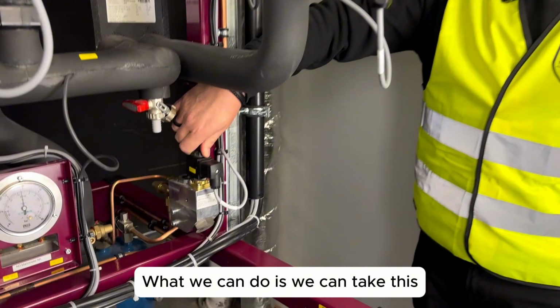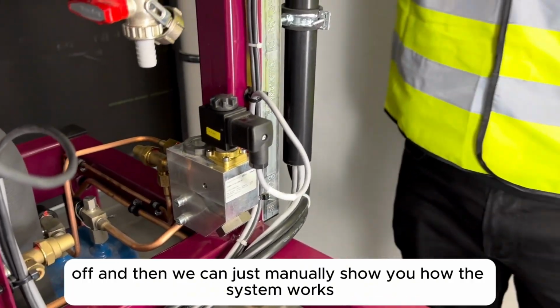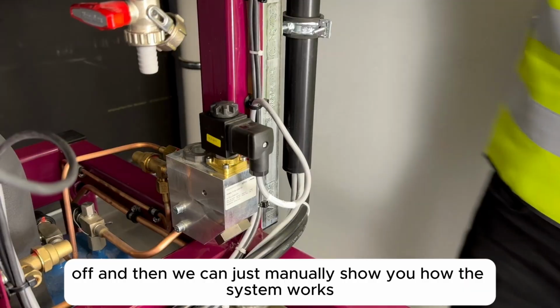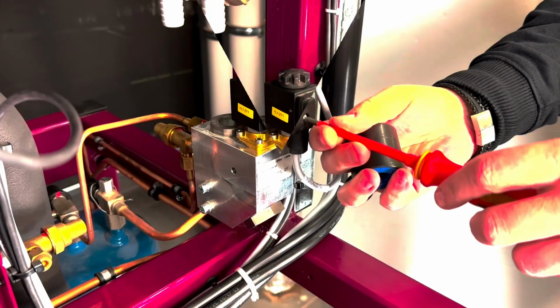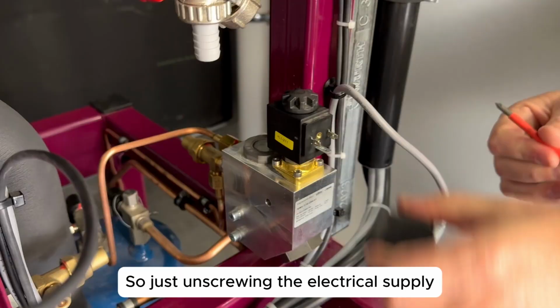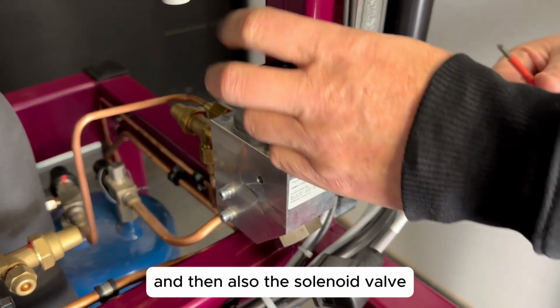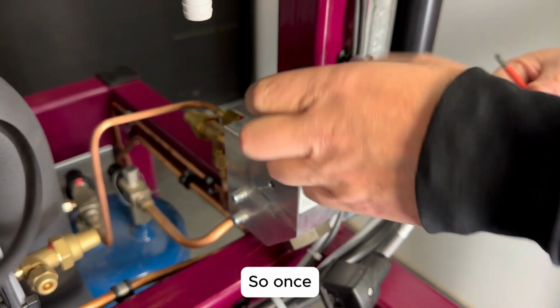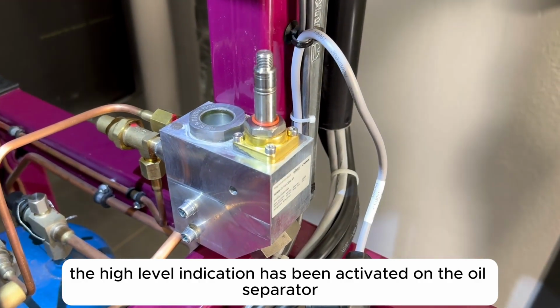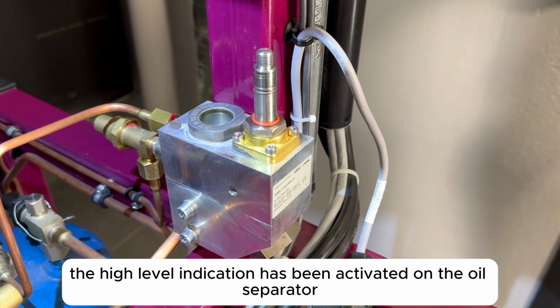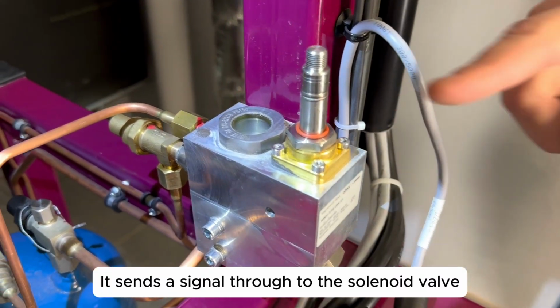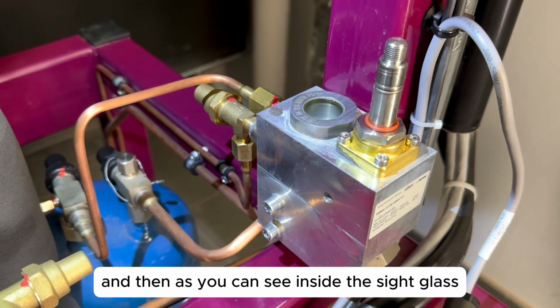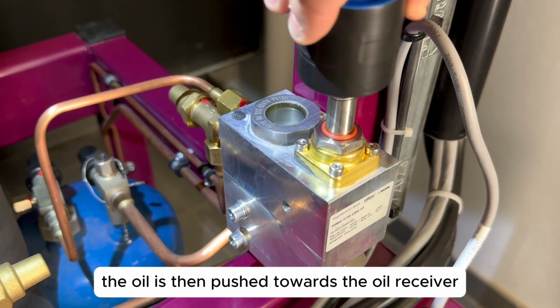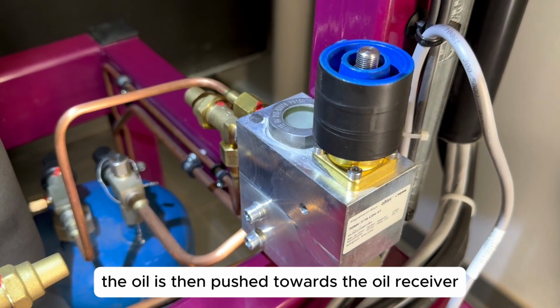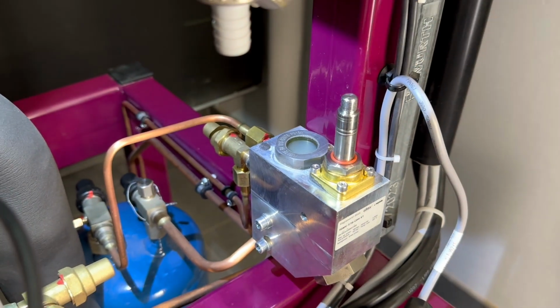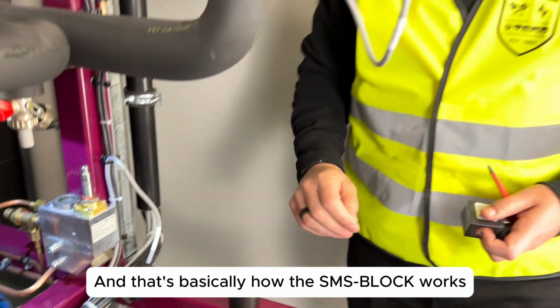What we can do is we can take this off, and then we can just manually show you how the system works. So just unscrewing the electrical supply and then also the solenoid valve. So once the high level indication has been activated on the oil separator, it sends a signal through to the solenoid valve, and then as you can see inside the sight glass, the oil is then pushed towards the oil receiver. And that's basically how the SMS block works.